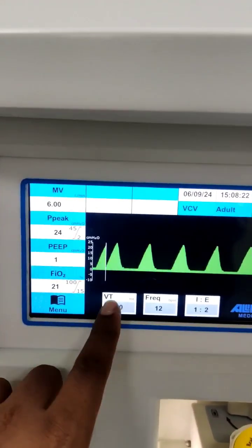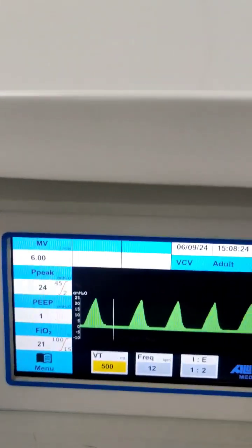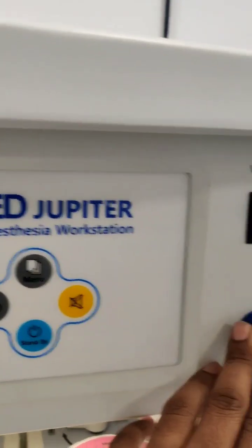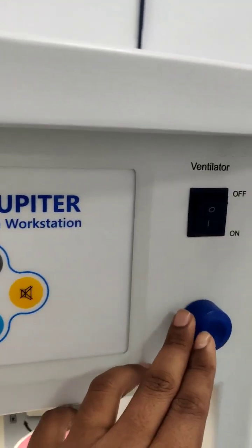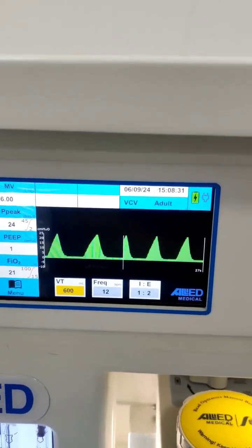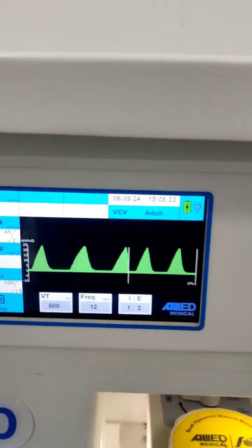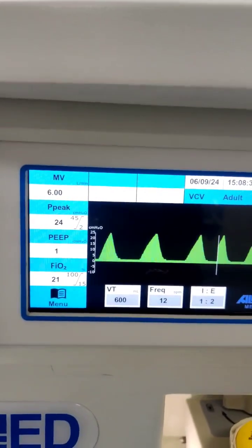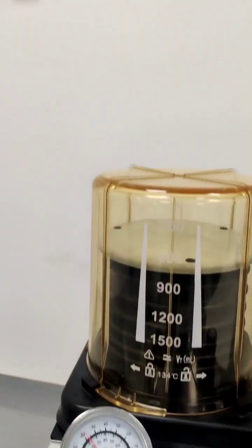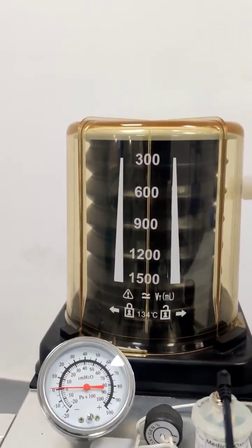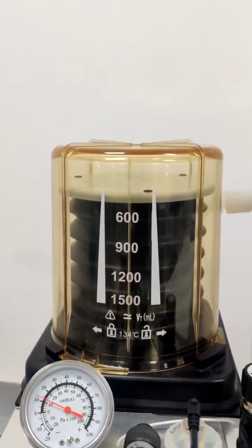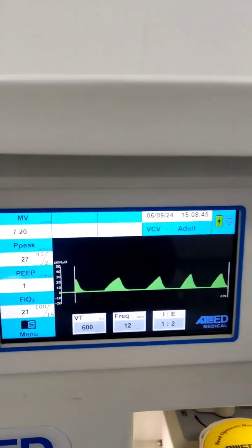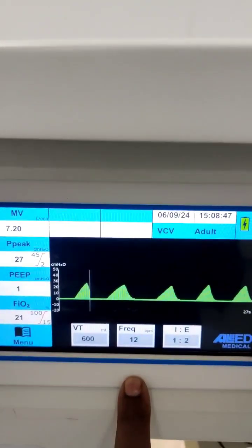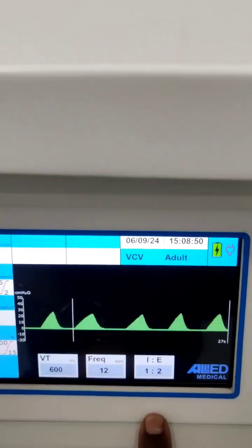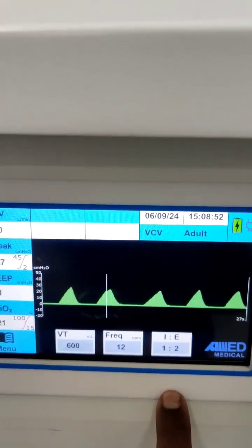The tidal volume is settable, so we can set it with the help of the knob over here. You can increase or decrease it with the knob. Right now I am increasing it to 600 ml. Whatever tidal volume is set can be measured and monitored with the help of the markings which we are giving on the bellows. The frequency is the breathing frequency, the respiration rate you can say. And the third setting is the I to E ratio.